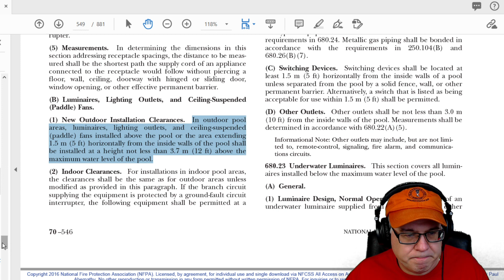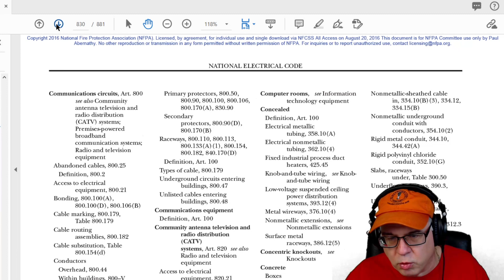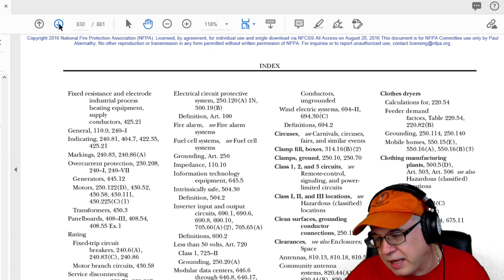So how would I look this one up? First, if I didn't know where to go, I'd go to the NEC, and I'll just use the index for those that are new. I'm going to go under... well, the first thing I could do is I'm already here, so you notice it says Class 1, Class 2 location, see hazardous. That would have pushed me into hazardous, so I'm going to go down to hazardous and see what we get.